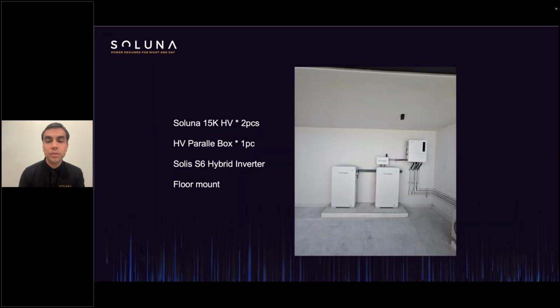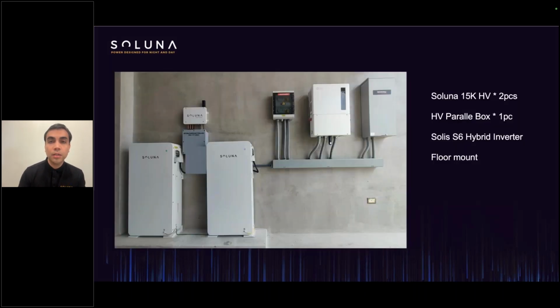This is another example. You will see multiple installs with 2 batteries, because if you think about the code in Canada, you are allowed up to 30 kilowatt hours in one residential home, with only one unit at a maximum of 20 kilowatt hours. So in this case, you have 13.5 kilowatt hours of usable capacity with our 15K. Then if you want to add another battery, you will just need to have 1 meter apart between each battery, and it will be within compliance.